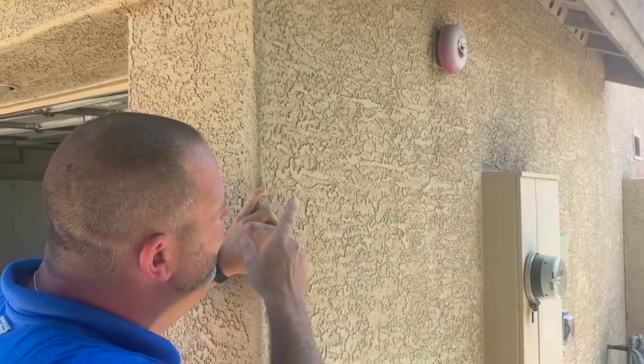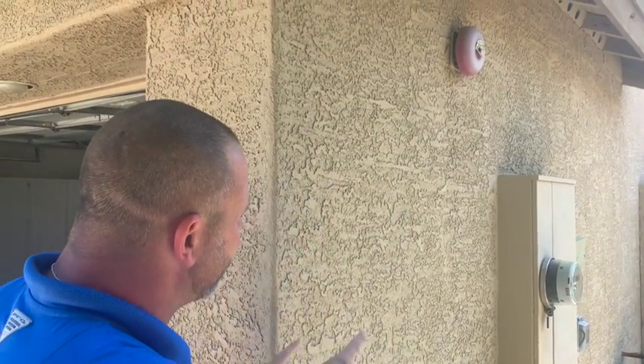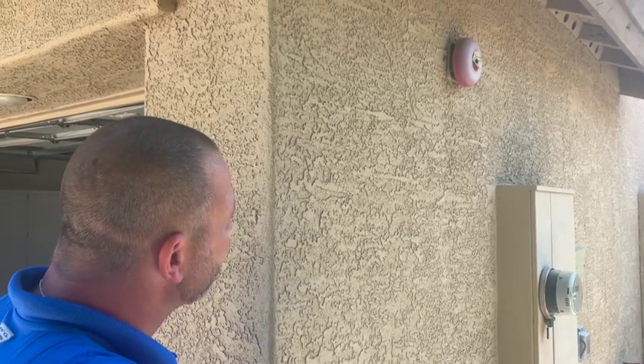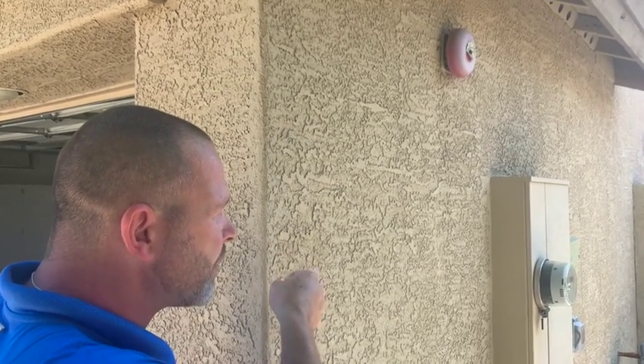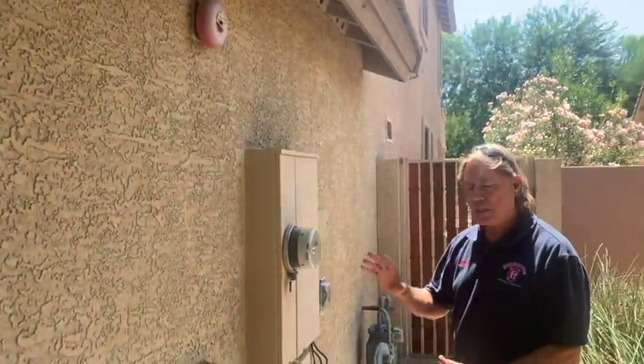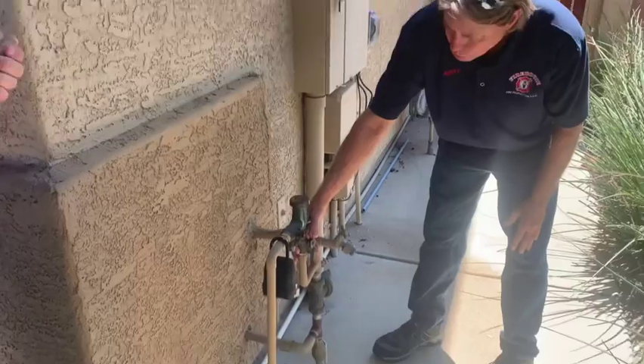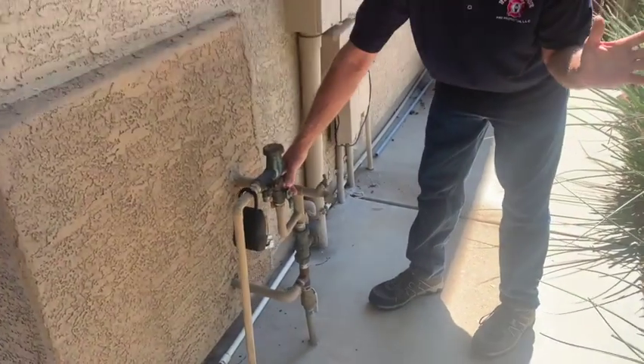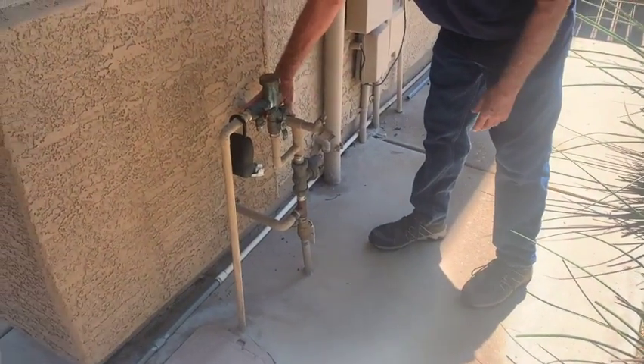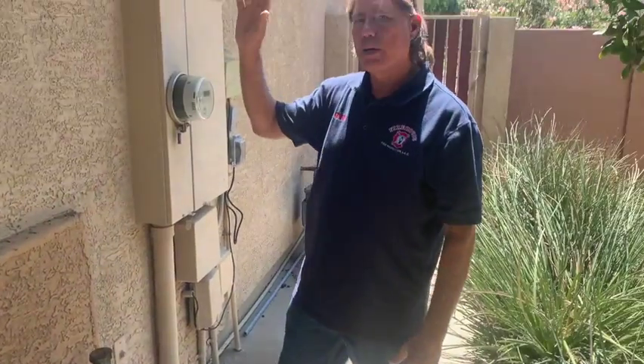The only time this bell is going off is if that contact is activated, which means there's water flowing through the system? Exactly. You have an isolation of systems here. So this is going to be our fire sprinkler. If you were going to run your irrigation, that should not impact the bell whatsoever, or anything in your domestic. It is not going to impact the flowing of the bell. Strictly the fire sprinklers. Excellent.